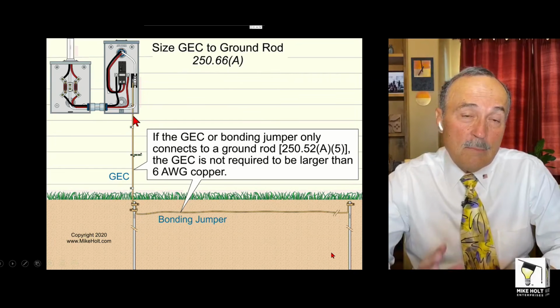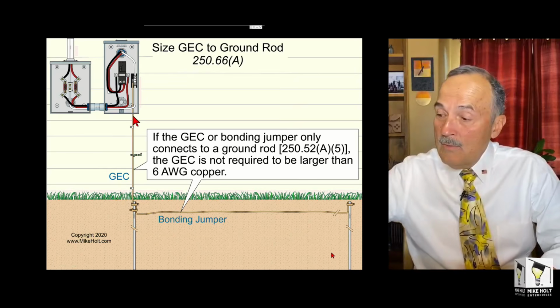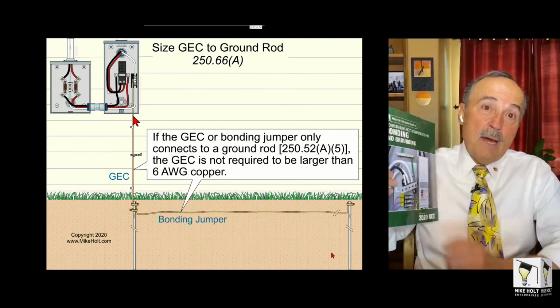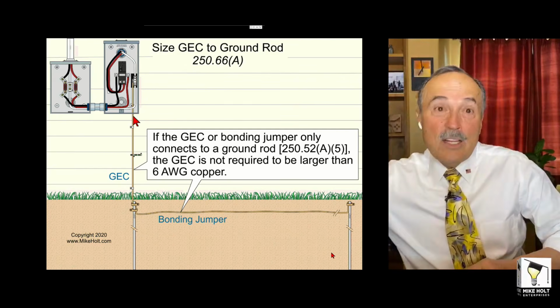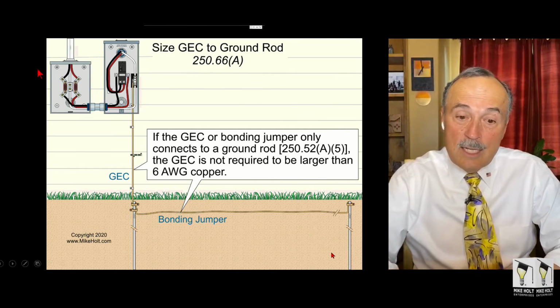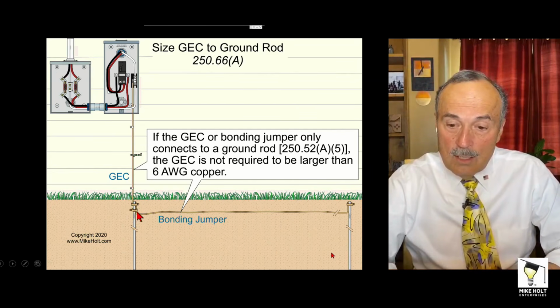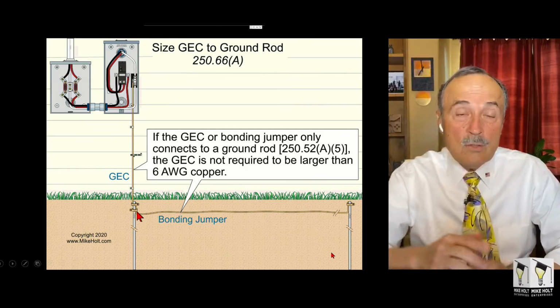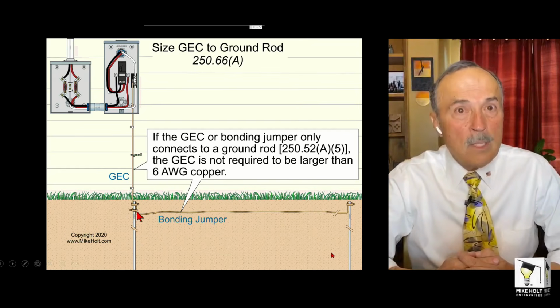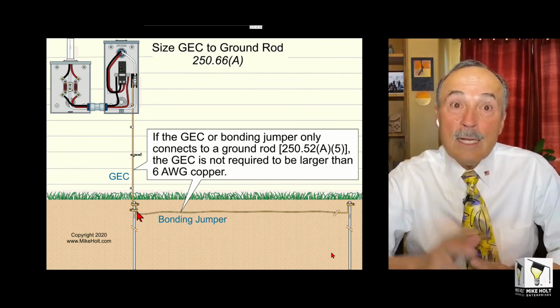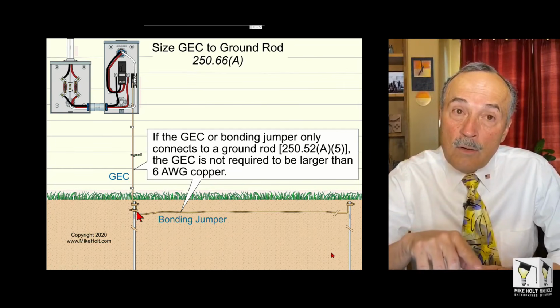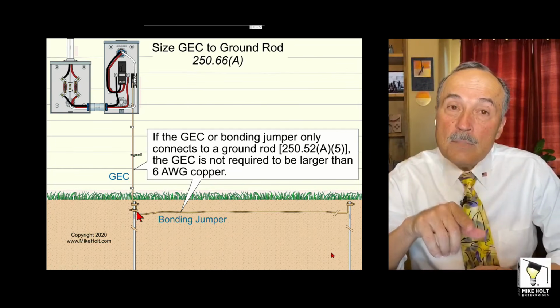Probably 99%, well, I'm saying 90, depends on whether or not you've ever taken my bonding and grounding classes. But other than people that have taken my bonding and grounding class, you know what? It's going to a ground rod. Guess what you're not carrying? You're not carrying current to a ground rod. You're not carrying fault current to a ground rod. So what the heck are you doing to a ground rod? That is called equipment grounding in this particular case.